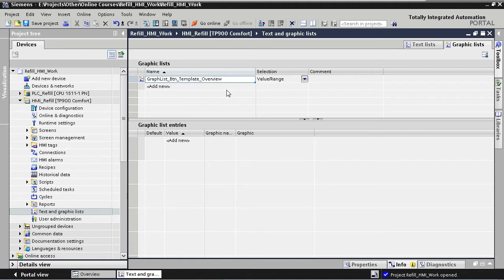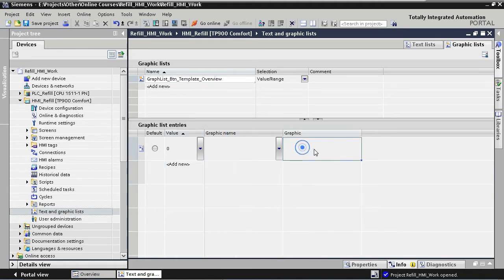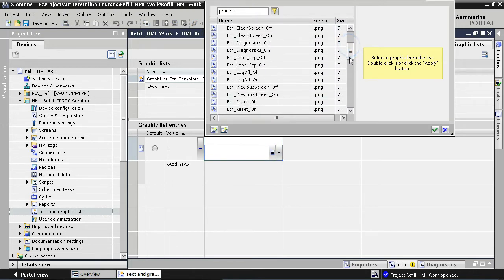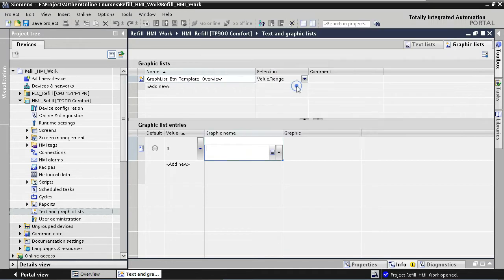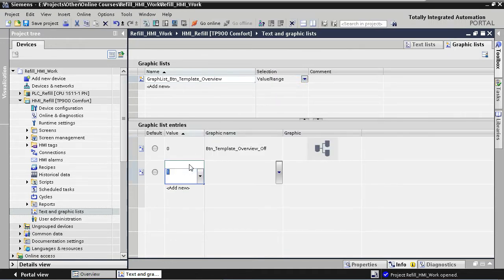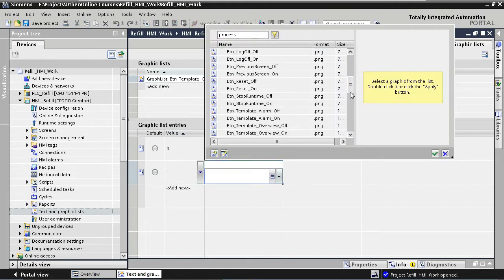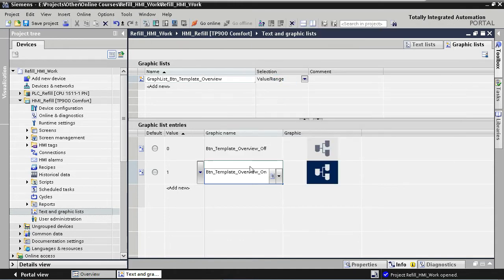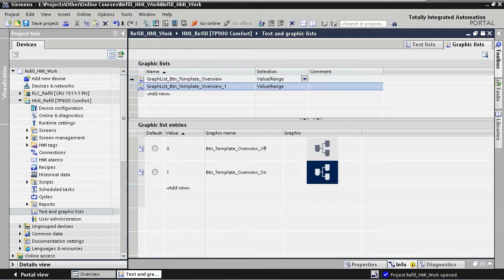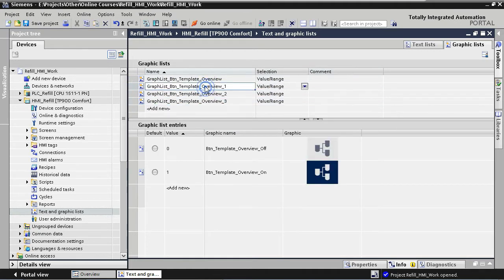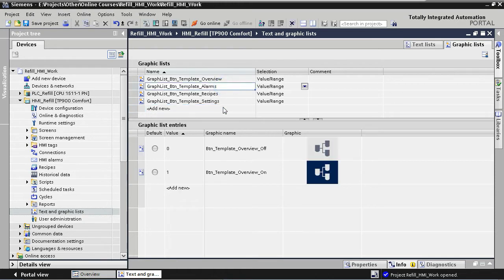Now we add our graphics under Graphic List Entries. We are going to add two graphics: one for our inactive state and a second one for our active state. We define the value for our inactive state as zero, and for our graphic we select 'Button Template Overview Off' from the library, which contains all the custom graphics imported in a previous lecture. Our second entry has the value one and we select 'Button Template Overview On' for our active state. Now we do the same for the graphic lists of our three other template buttons, starting by copying the existing graphic list three times and renaming them according to our main screen buttons. Then we dive into each graphic list and change the graphics accordingly.